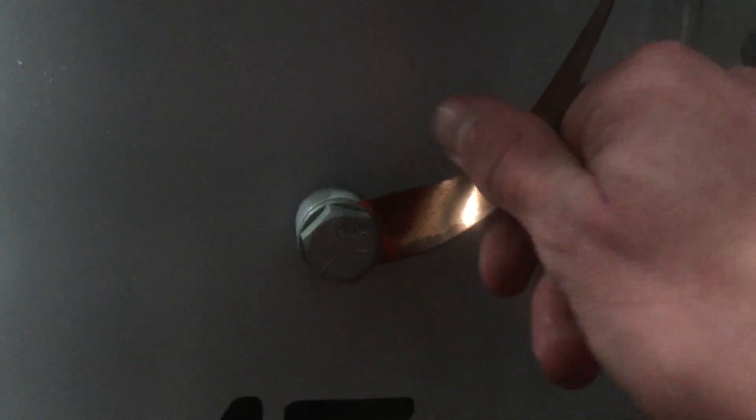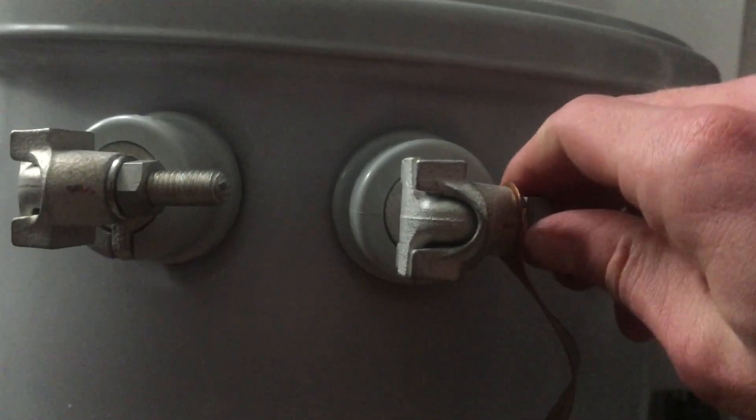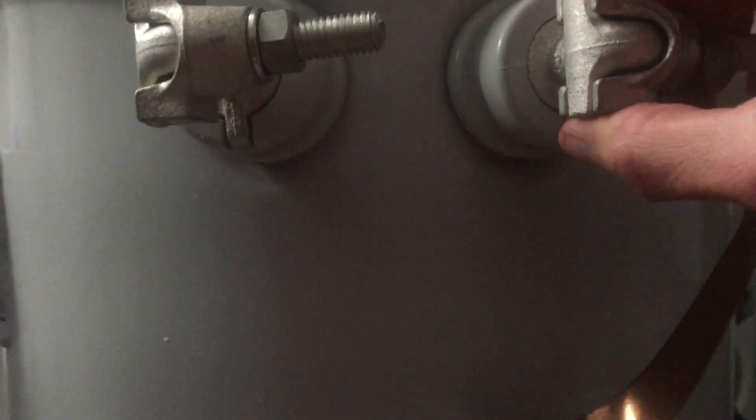Definitely a good price for what I paid. So this here is on the low setting of 7200, and then click that up one to 14400. And I believe this is the oil drain here. The ground terminal — this is actually some pretty big bus bar almost — and these huge terminals. Wonder how many amps this can pull through: 15 kVA is rated for, I believe, 75 amps continuous at 240 volts.